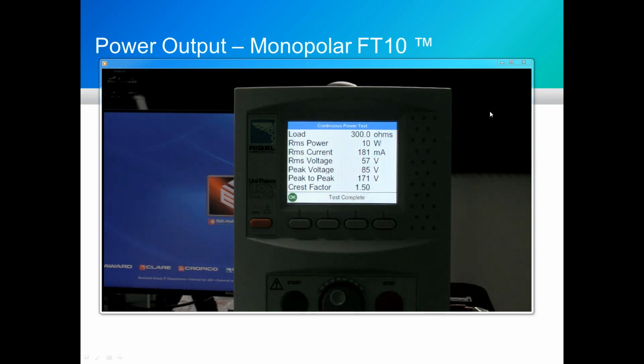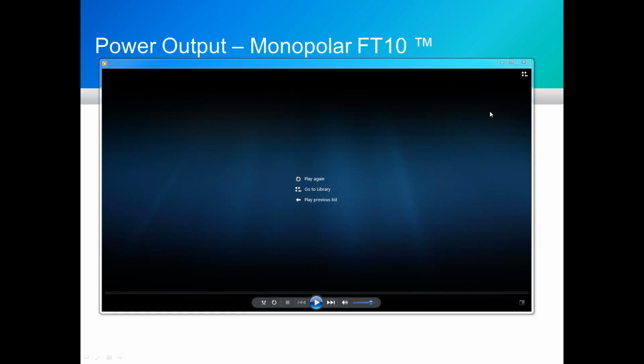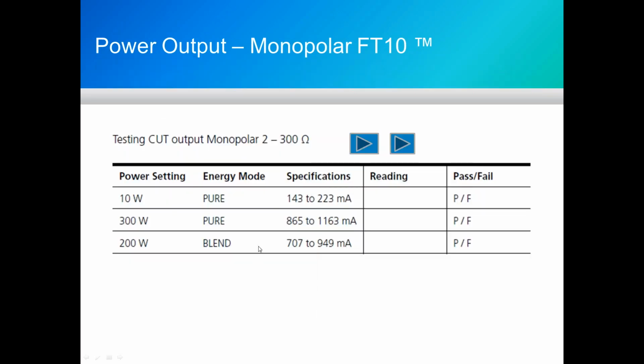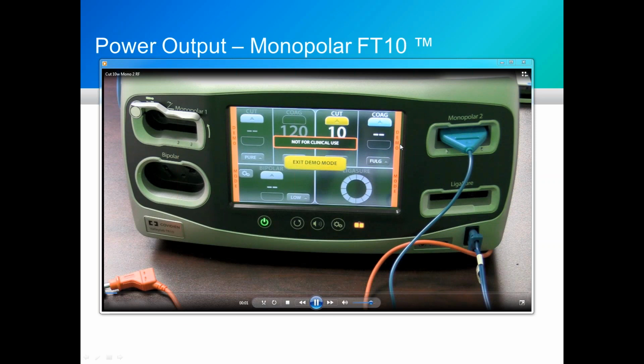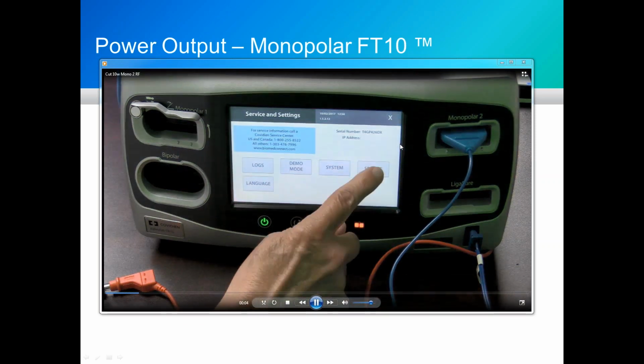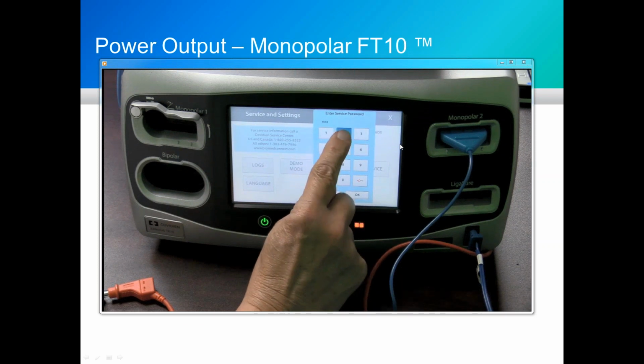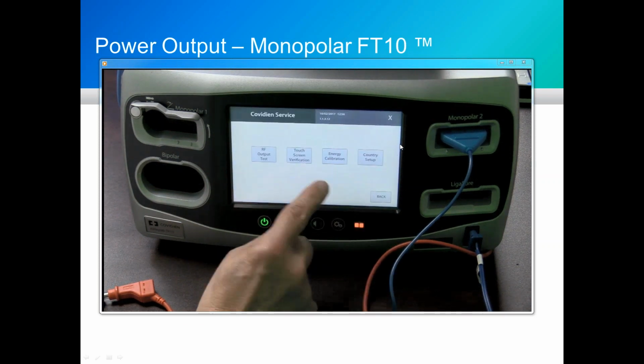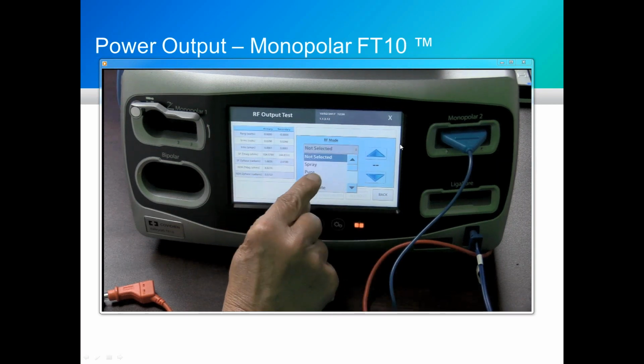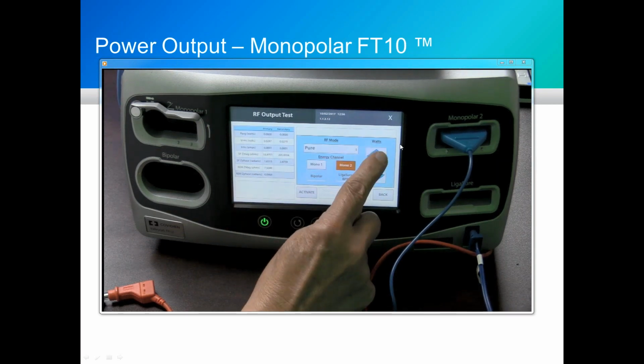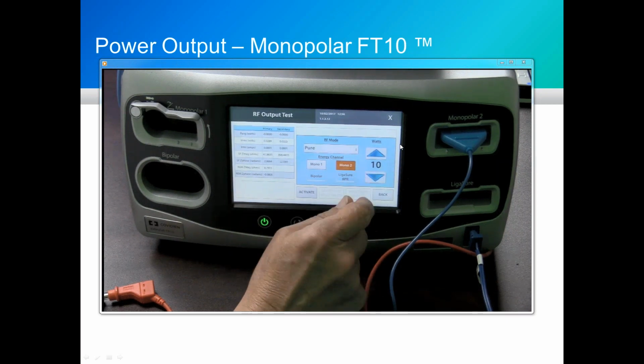And again, of importance here would be what that current value is, 181 milliamps. That will be the driving factor as to whether the service manual says that is good or not. And as we see, our acceptable range was 143 to 223, so everything is proceeding nicely for us. Now I'm going to do the same thing, but I'm going to go into service mode. So I'm selecting Monopolar 2, pure, setting for 10 watts.